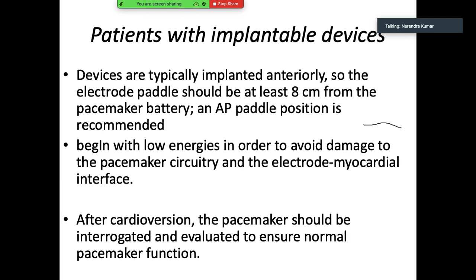Actually, one should always prefer, because we are aware that most of the time those devices are implanted anteriorly, right? So whenever you're placing the paddle, the minimum distance is at least 8 to 10 centimeters, okay? And AP, not anterolateral. Oh, I'm still far away from the device so I will put it in the anterolateral position? No, anteroposterior position should be recommended, in fact, and always begin with lower energy. Otherwise you can damage the pacemaker circuit or even the electrode-myocardial interface. Once you're done, always call the physiologist to look at the pacemaker, do the interrogation, and evaluate whether it is still working well or not.